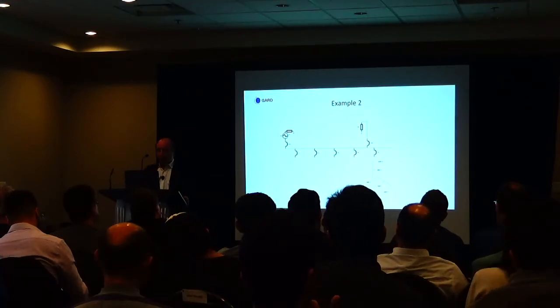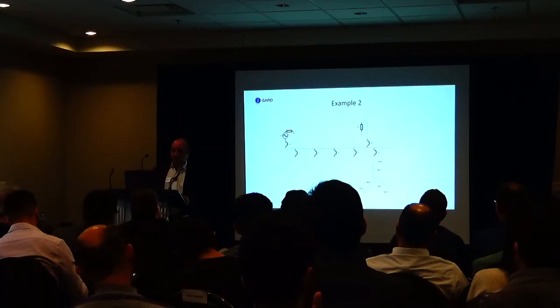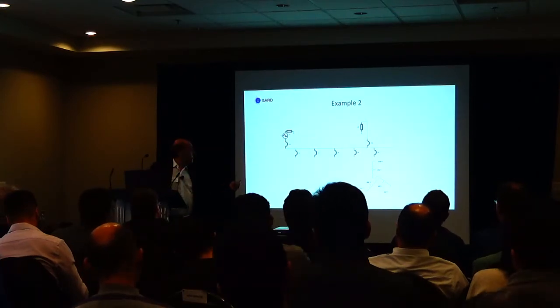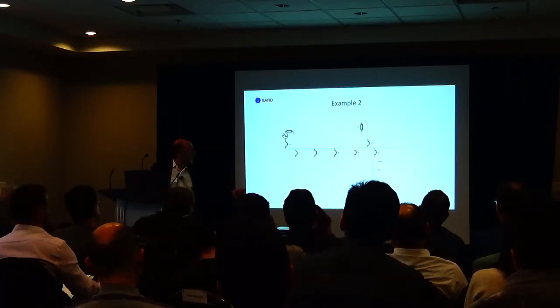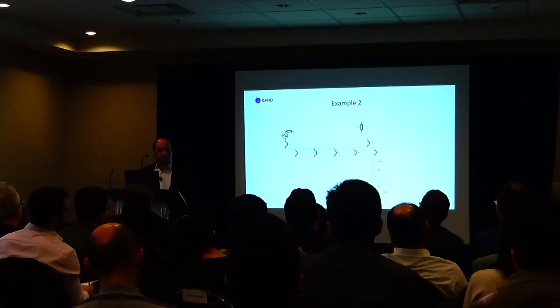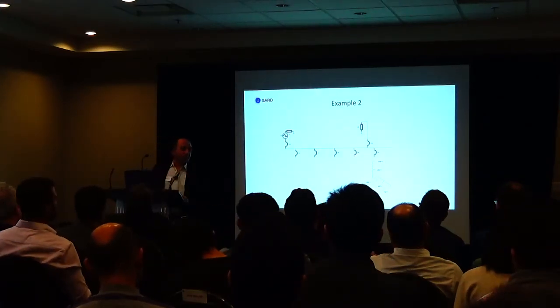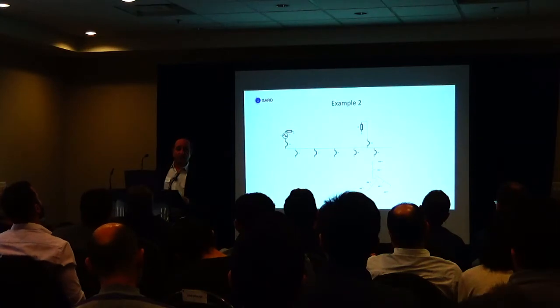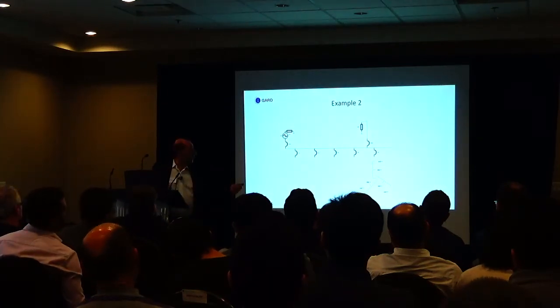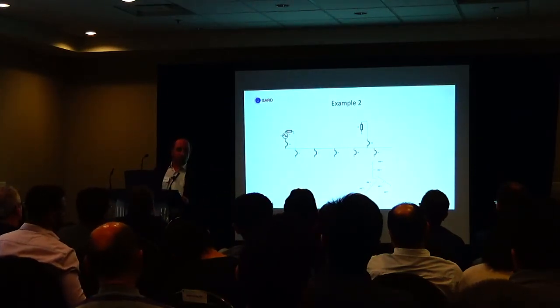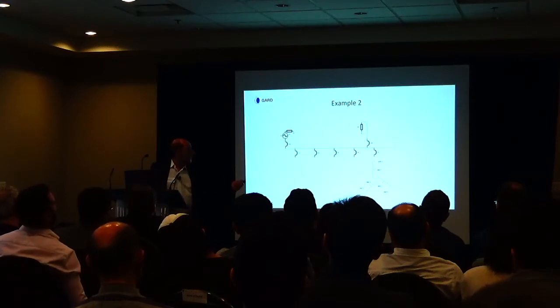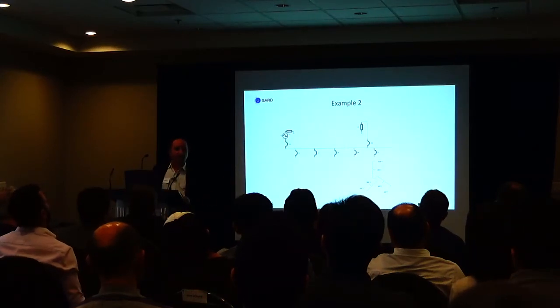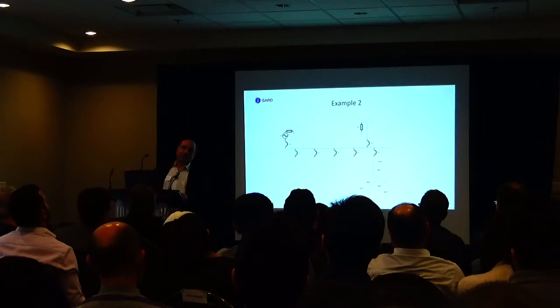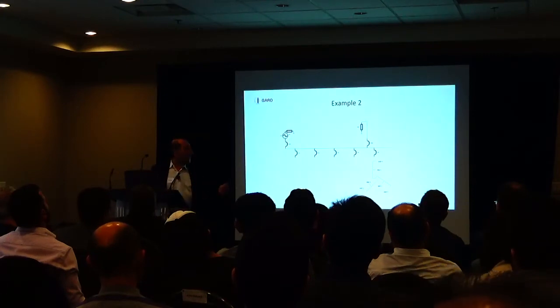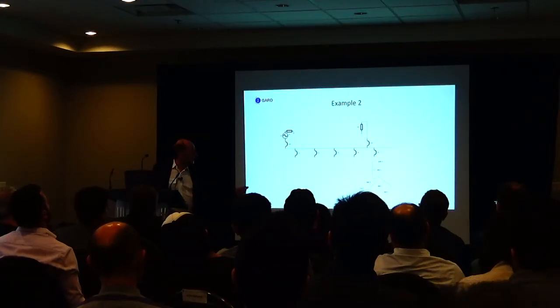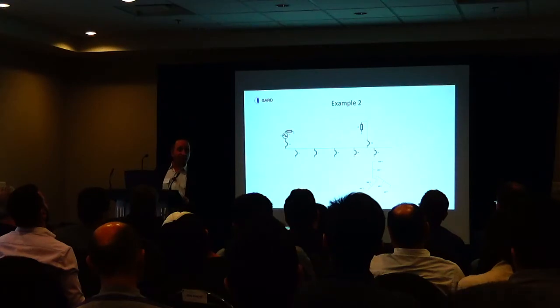We have another system where they had a generator and a transformer, and when they were commissioning it, they were blowing the fuses. They couldn't understand why they were blowing fuses all the time. Now this transformer had no distributed neutral. This transformer went directly to the resistor and tied to ground. They measured the ohmic value, 69 ohms. They had a ground fault and destroyed all the cables that are going in here. So you knew something was wrong.